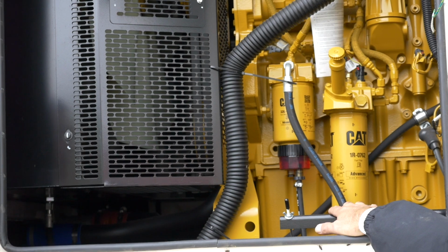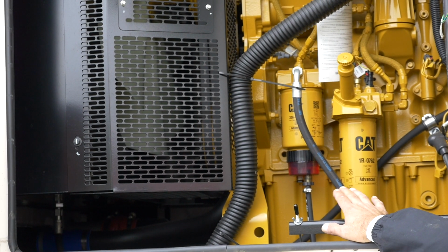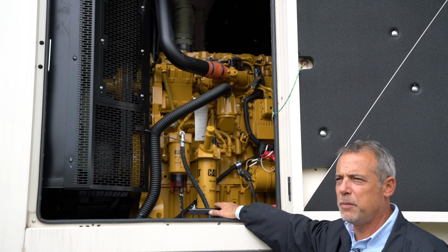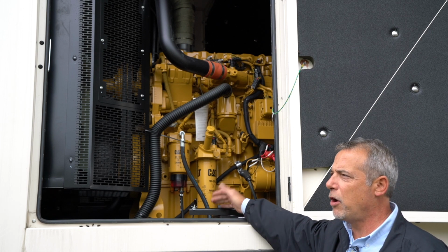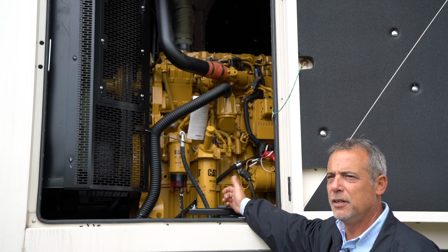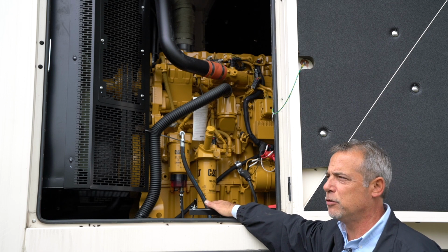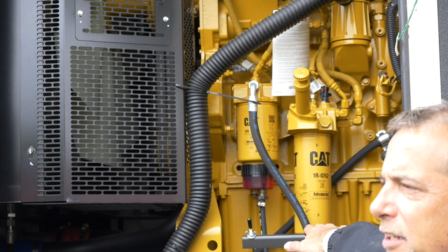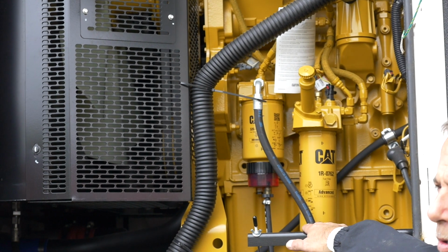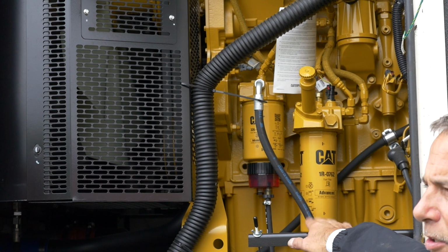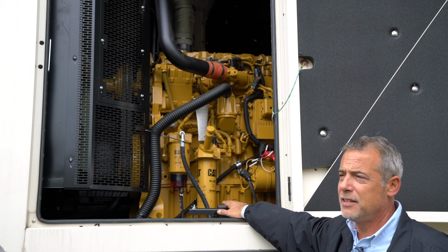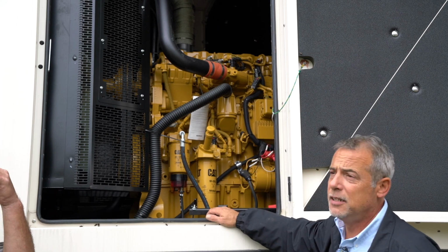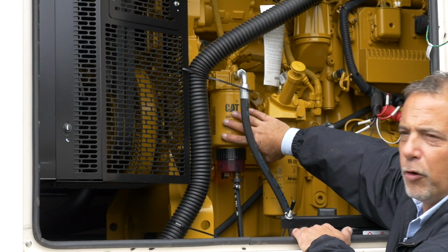They say maintenance free. They're not. Caterpillar doesn't sell a generator with maintenance-free batteries in it. They have issues with maintenance-free batteries boiling over because it's always trickle charging. And we had a lot of battery failures because nobody can check them. If you do have to add to them, only add distilled water. Never add battery acid back to the battery. Like I said, they say maintenance free, but if they have removable lids like this has on it, it's not maintenance free. You have 2 fuel filters.